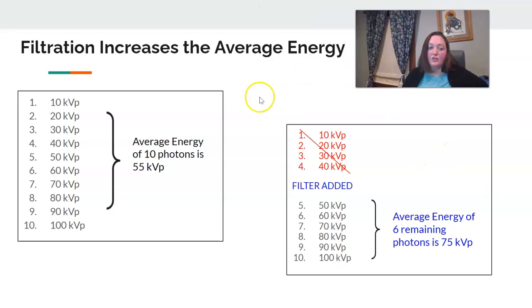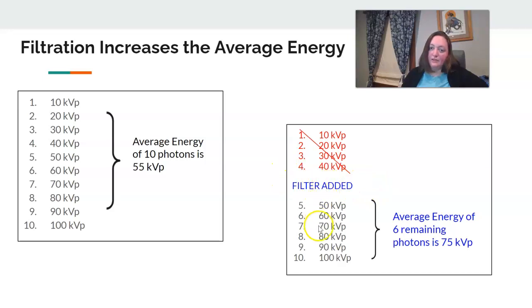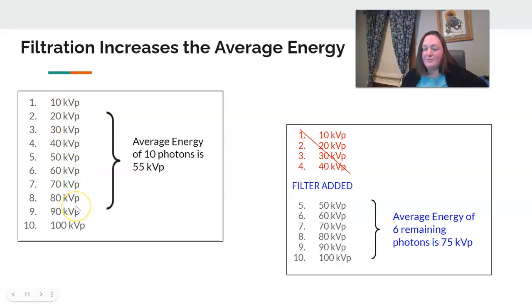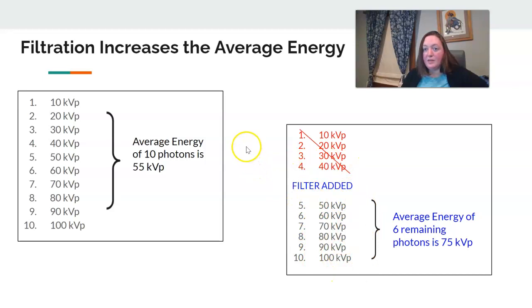Here's an example of how filtration increases the average energy. If we have a collection of 10 KVP values, the average energy of those 10 is 55. If I remove four of those by adding in a filter, the average of the remaining ones is higher. Those lower-energy stragglers get kicked out, and the remaining energies of the beam are collected, giving a new average with higher energy.